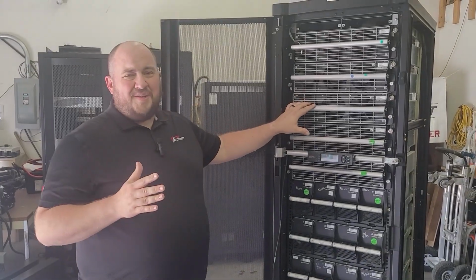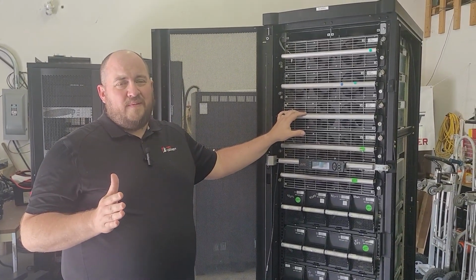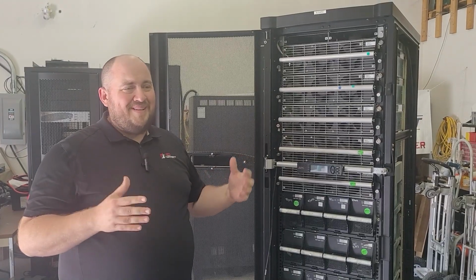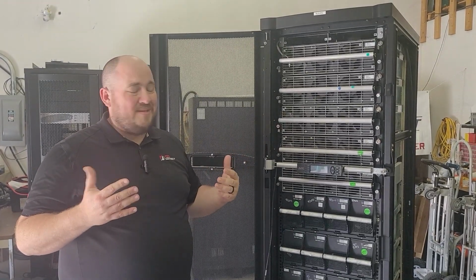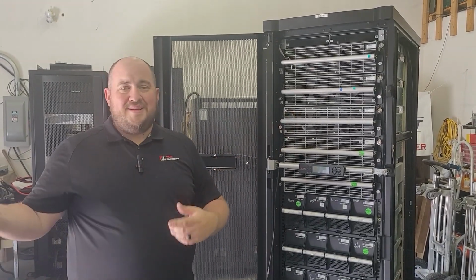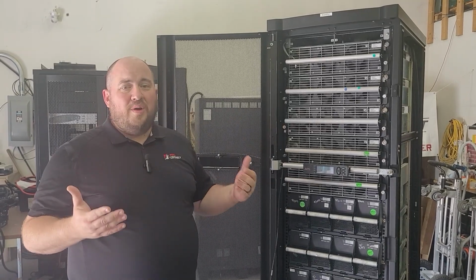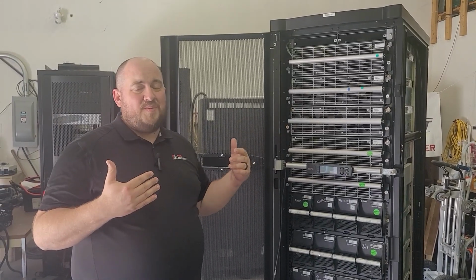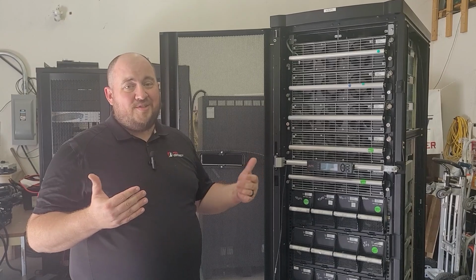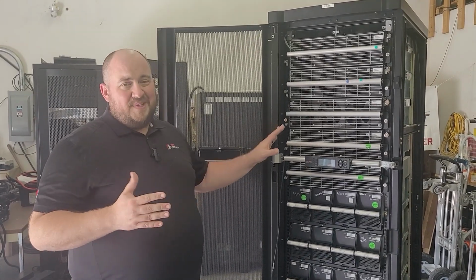Okay, these modules also are not really repairable when they fail. Everything is soldered into a board. It's not really made for component repairs. At that point, you're pulling one out, you're tossing it, you're putting a new one in. Newer APC modules have lifetimers on those modules that need APC factory support just to reset the timer. This one does not have that.